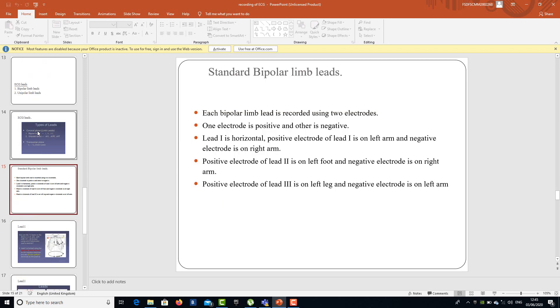Each standard bipolar limb lead is recorded using two electrodes — one positive and one negative. Lead 1 is horizontal: the positive electrode is on the left arm and the negative electrode is on the right arm. Lead 2: the positive electrode is on the left foot and the negative electrode is on the right arm. Lead 3: the positive electrode is on the left leg and the negative electrode is on the left arm.